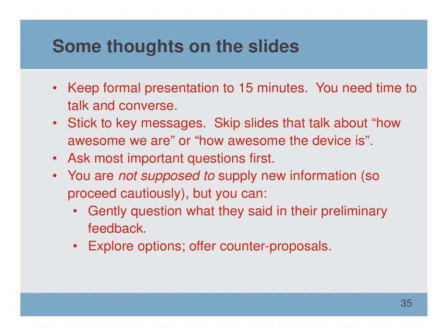So some thoughts on that slide preparation. Try to keep the formal presentation to 15 minutes. Review the device description, review the indication, review a few key points, and after 15 minutes say, here's our first question. Make sure you stick to the key messages. Skip any slides that talk about how awesome we are or how awesome the device is. Yeah, it's kind of nice to say, wow, we've been at this for 20 years or we've got the world's leading experts involved in this, but that's not what FDA is concerned about. You've got questions, they're going to try to give you answers. So ask the most important questions first.